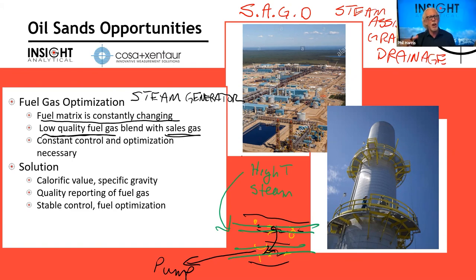So now we want the Wobbe Index analyzer there to adjust to those changes in composition and try to optimize how much steam we make. We want to burn the least amount of fuel to make the most amount of steam. So our solution to this customer issue is to measure the calorific value, measure how much energy is in the fuel, measure its density, because that's going to affect how it flows into the burner, and use that to control the burner. We can also make reports back on quality.